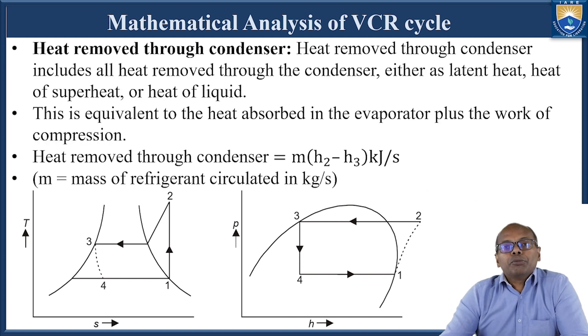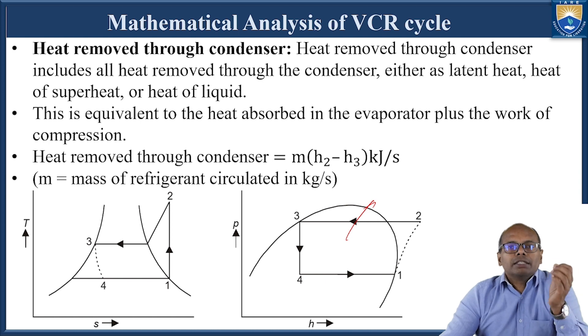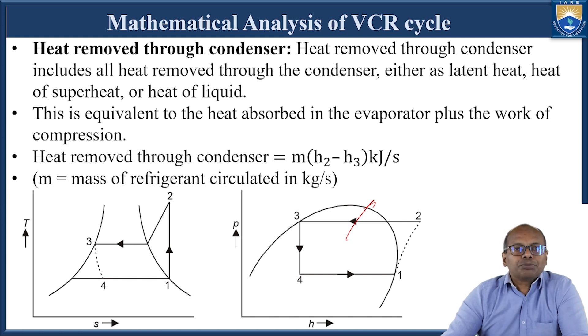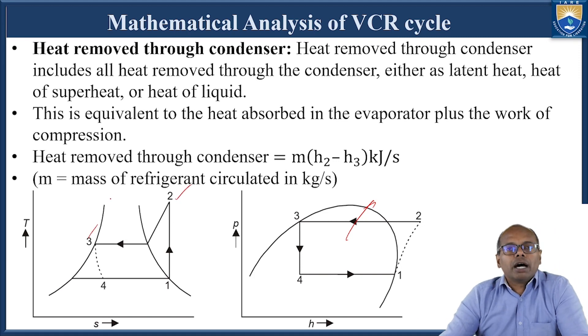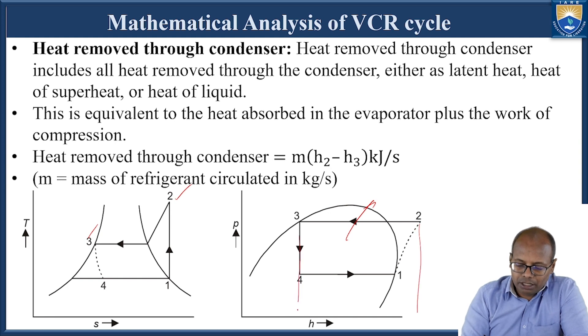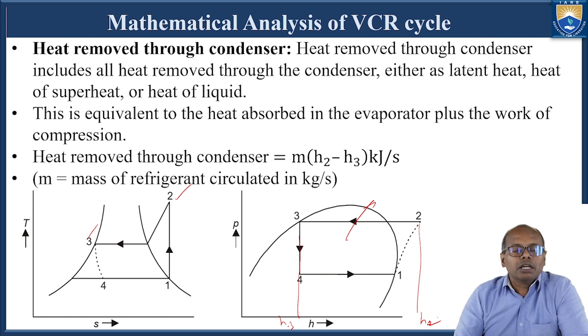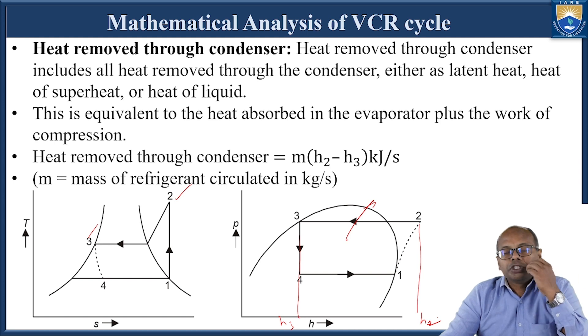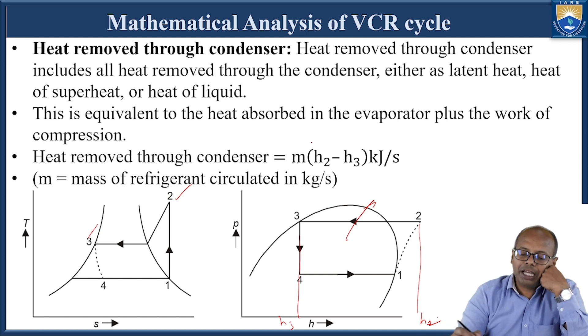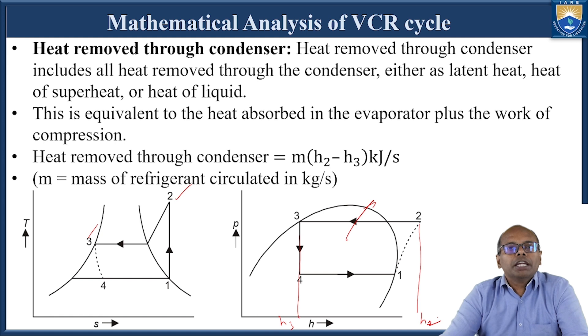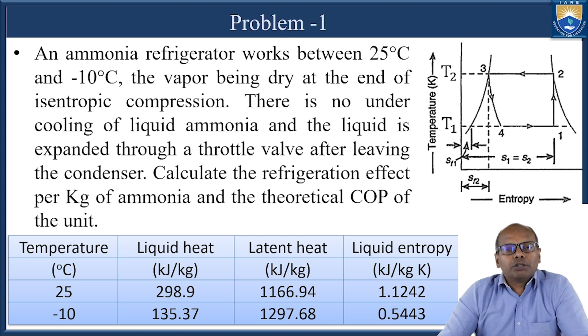The final parameter is heat removed through the condenser. This is nothing but the change in enthalpy during the condensing process from point 2 to point 3, given by H2 minus H3, where H2 is on the higher side and H3 is on the lower side. Multiplying by mass flow rate gives heat removed through the condenser in kJ/s. Now we will see two problems to wind up this session.